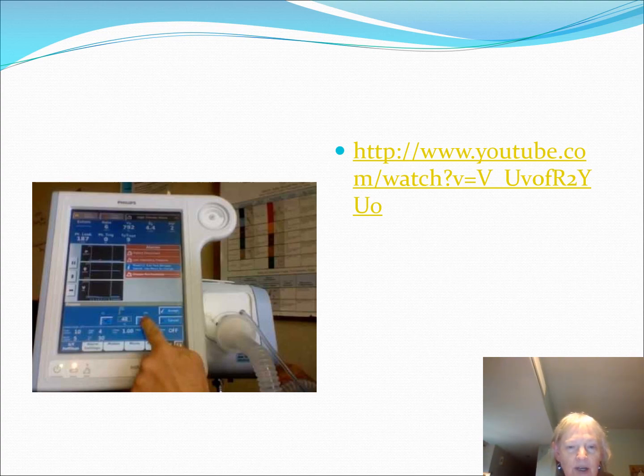Here's the clear circuit. These circuits are designed for the CPAP and BiPAP machines. These are not circuits you're going to find on your mechanical ventilators, and they're really not circuits we're cutting from the blue tubing. There's a different inside. It's a whole lot smoother so that the gas doesn't have much interruption. So you can come down here, make your changes, and then you can come up here and run your finger around this, and that will change it for you, and press the button and it sets it for you too. So that's a new one that's out there. A really, really nice machine to handle.